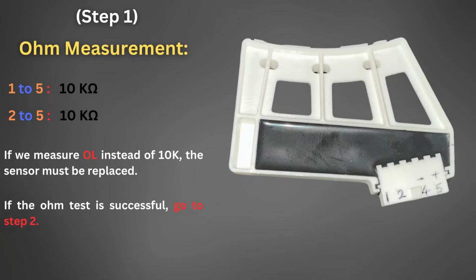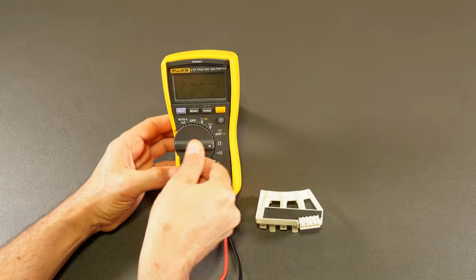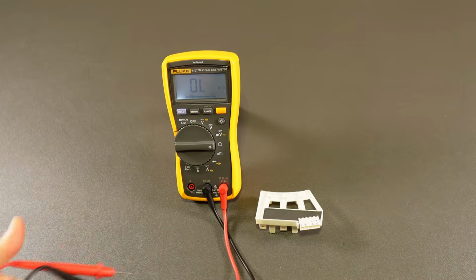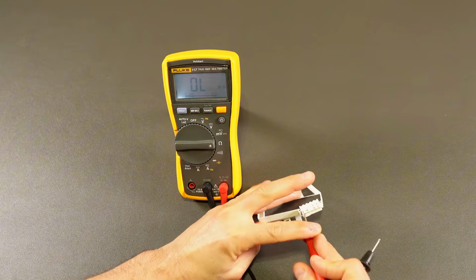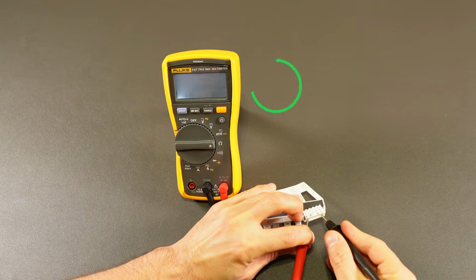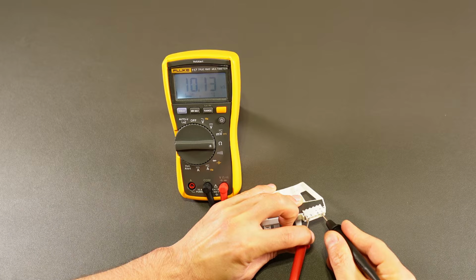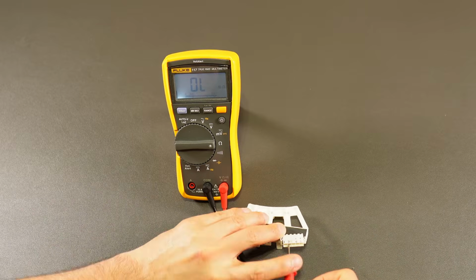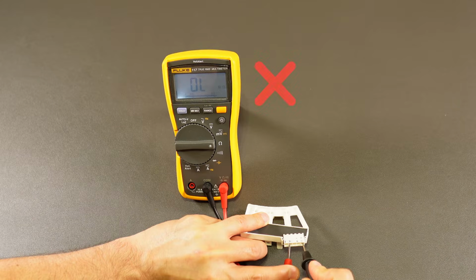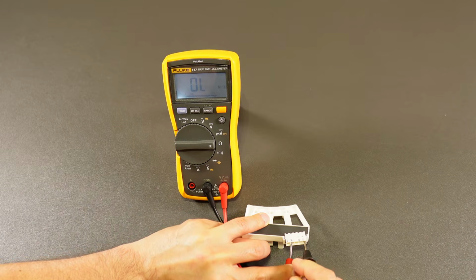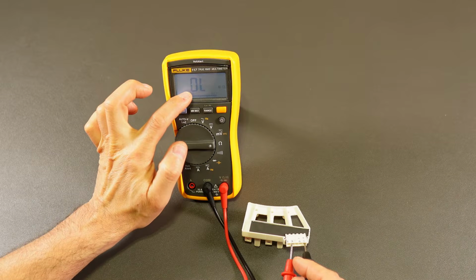The first step is the ohm test. The resistance between pin 5 and pin 1 as well as pin 5 and pin 2 should be roughly 10 kiloohms. If either test shows an open circuit, the Hall sensor is defective and must be replaced. The resistance between pin 5 and pin 2 is showing OL, so the sensor is defective and must be replaced.